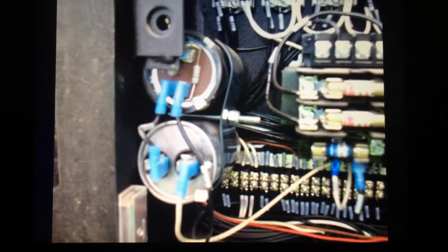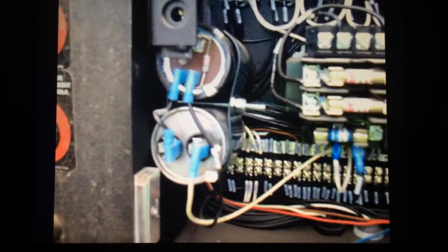This unit has two capacitors. We did the same procedure on both of them. We did them one at a time independently, removing the wires, discharging the electrical current in the circuit that's inside, tested the bottom one, reattached the wires, came up to the top one, disconnected those wires, discharged the capacitor, and checked the reading on the microfarad. Compare that with what is on the outside of the jacket right there. It'll give you a reading of where the allowable limits are for microfarad. Both of these passed just fine, so we know we don't have a bad capacitor. In a lot of cases, it's just the start capacitor that we can replace, and then we're good to go. By and large, that's going to be the problem for a hard start on an electric motor. In this case, the capacitors were fine.